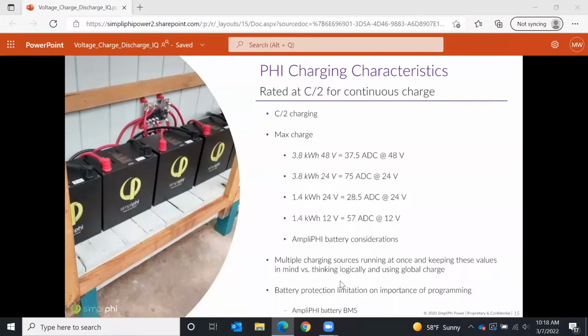Again, if you're using LFP batteries, you need to make sure to program the charge and discharge rate into the system. But if you're using the SimpliPhi battery, this is actually going to program itself, even if it's undersized, programming the inverter's charge and discharge rate for you.